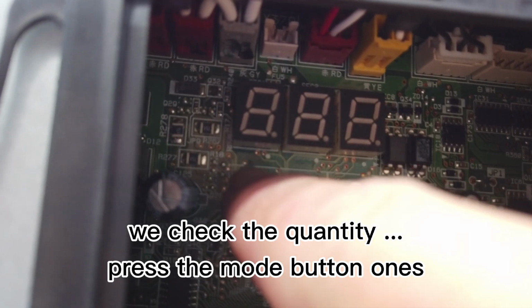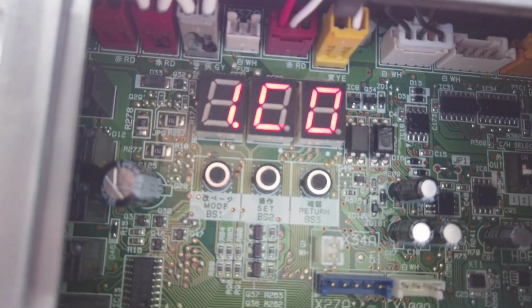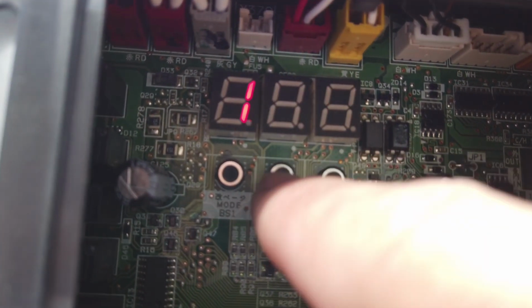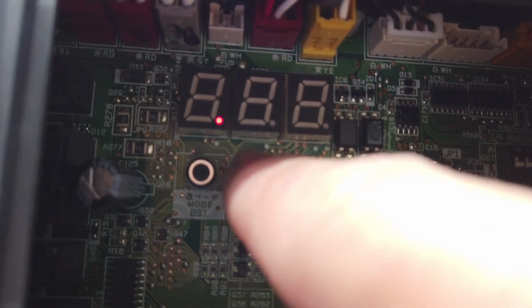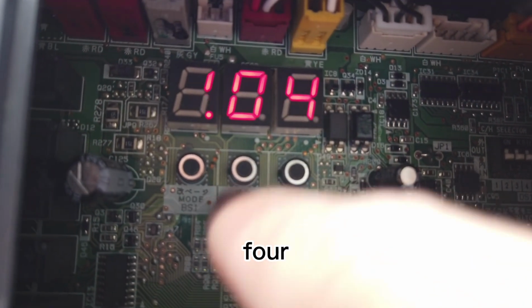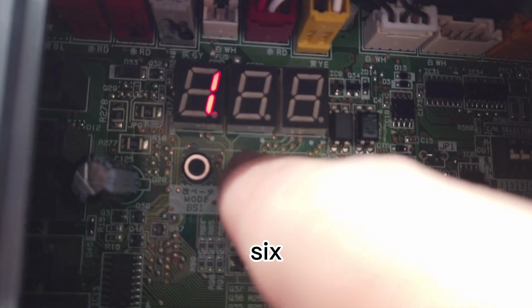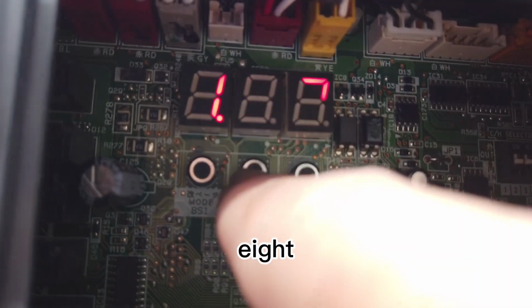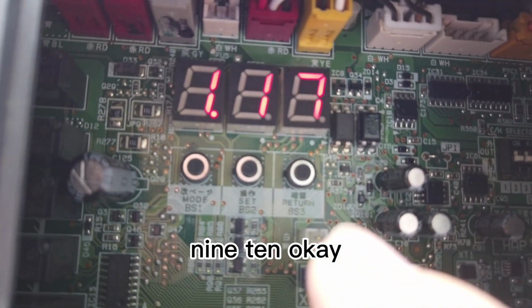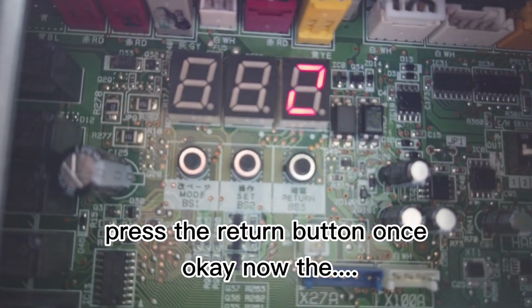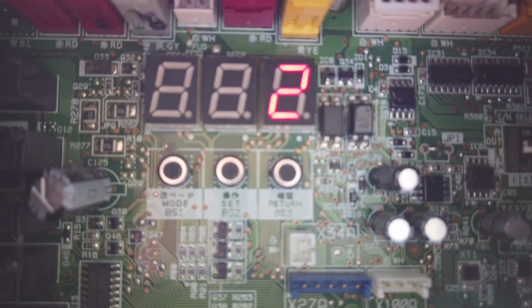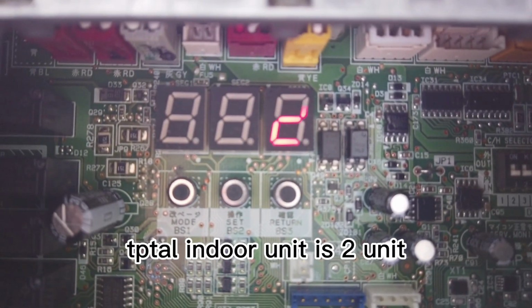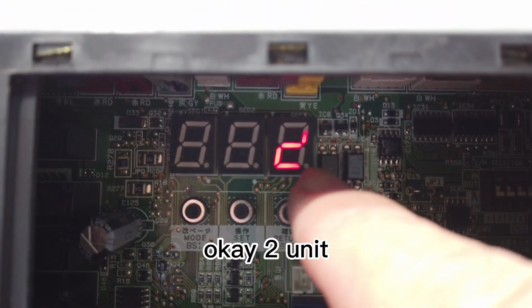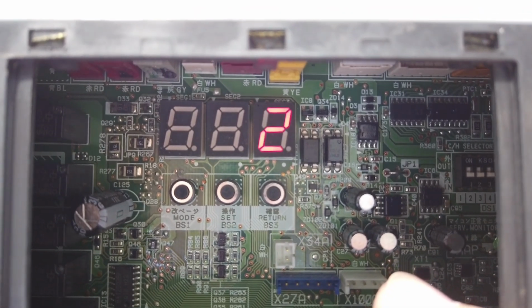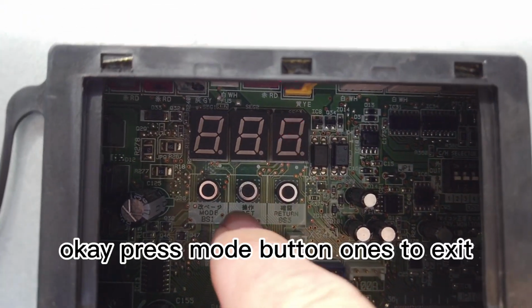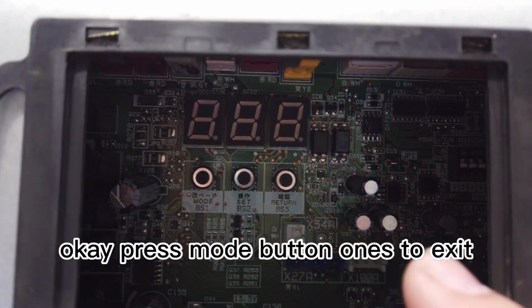We check the quantity. Press the mode button once. Press the set button 10 times. 1, 2, 3, 4, 5, 6, 7, 8, 9, 10. Okay, press the return button once. Okay, now the total indoor unit is 2 units. Okay, 2 units. Okay, press the mode button once to exit.